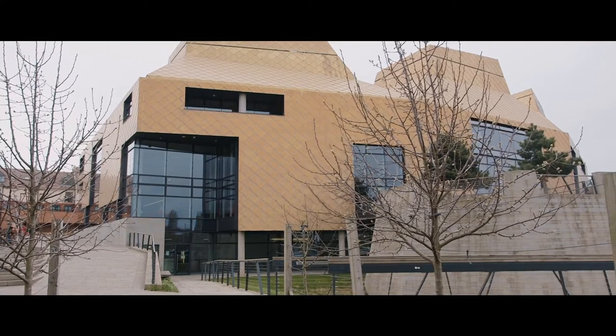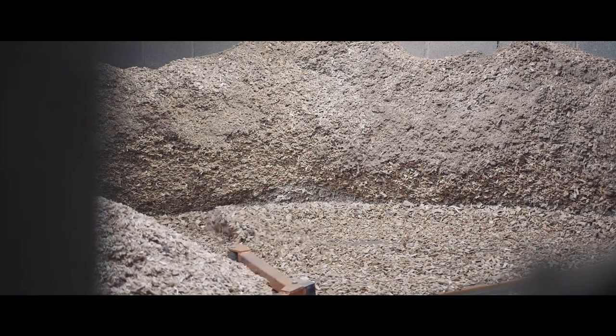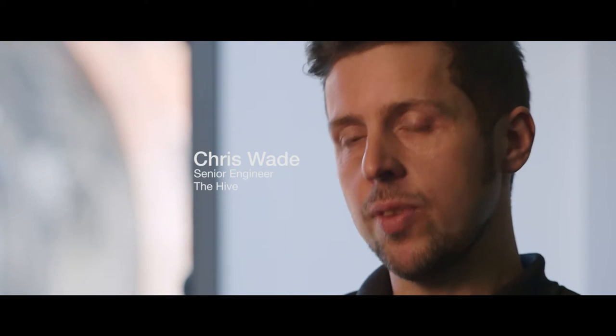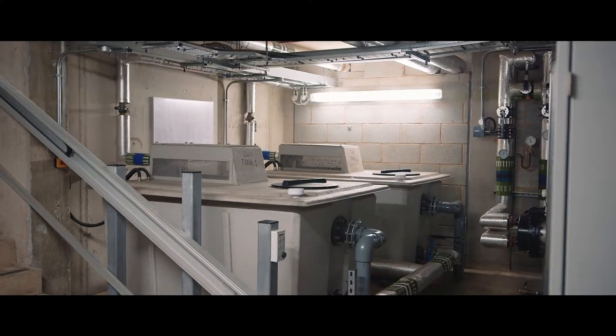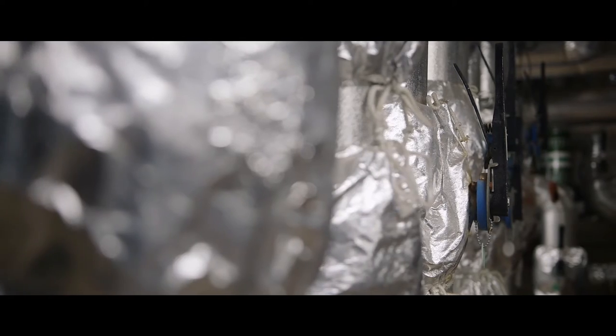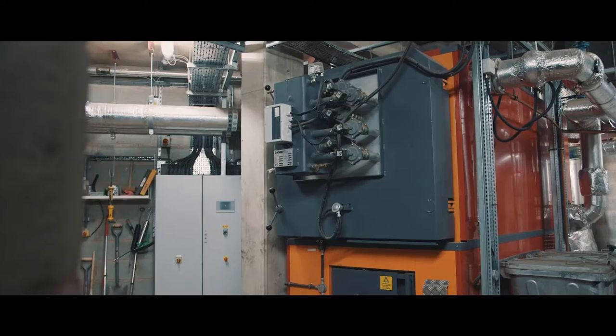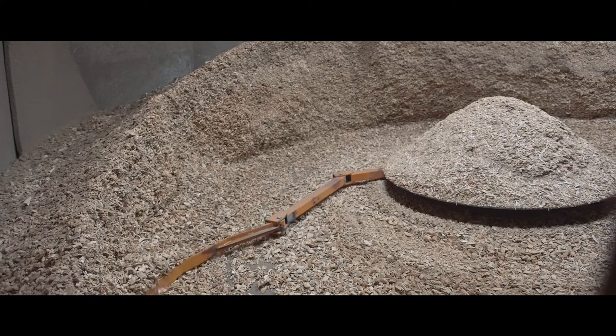Hive has been designed as a passive building, so it's made to use as little external input as possible and use as many of the available resources around the Hive as possible — natural light, natural ventilation, natural cooling and natural heating if possible. It's been built as a high thermal mass building, so we've got large amounts of concrete slab within the building, and these will retain any heat and also any cooling in the summer. We use the air flow through the building, open windows, and encourage a chimney stack effect, which draws cold air in during the summer months and cools the building down so we don't have to use forced cooling supplies.